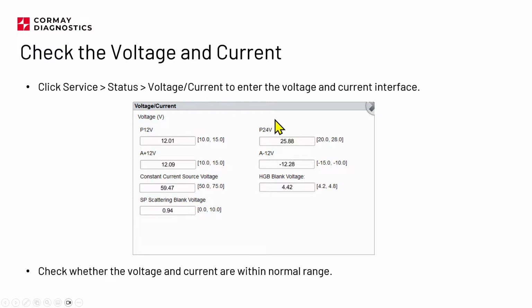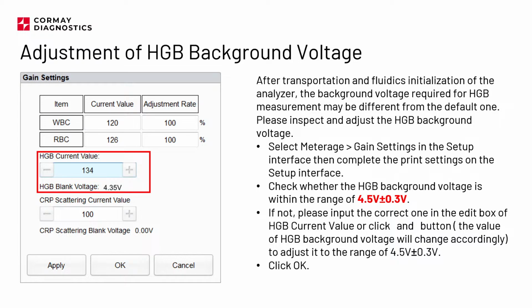Another menu, this is voltage and current. What will be important here? We need to check the hemoglobin blank voltage, and also we need to check what is the scattering blank voltage, those two things. And later, if the hemoglobin blank voltage is a little bit too high or a little bit too low, we can have a situation that the analyzer will give us an error message that the hemoglobin blank voltage is too high or too low, and in that case you will need to set the gains or current value for this sensor manually, right? And this is the range in which the sensor should be set.